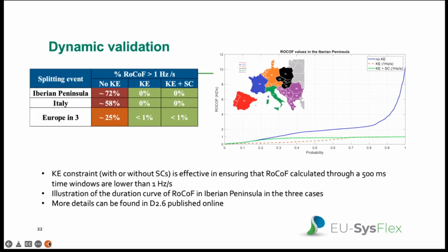As an example, the figure to the right illustrates the monotonic function of the RoCoF values in the Iberian Peninsula zone following the splits, assessed over each 500 millisecond period for different cases. As can be seen, RoCoF can reach more than 10 hertz per second without inertial constraints, which is not manageable by system operators in practice, but remains under 1 hertz per second with the help of the implemented inertial constraints and additional synchronous condensers.